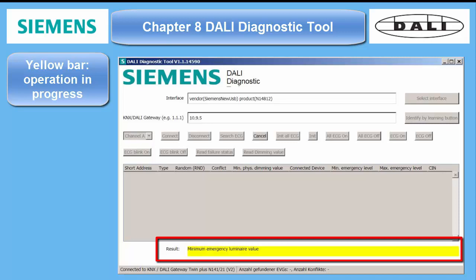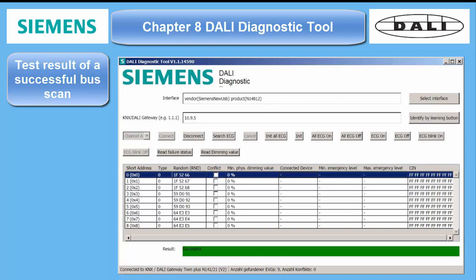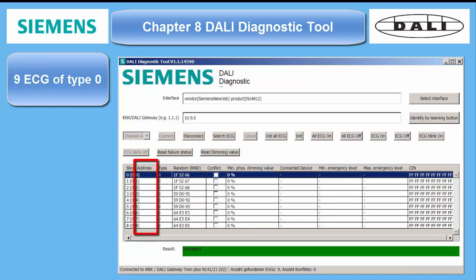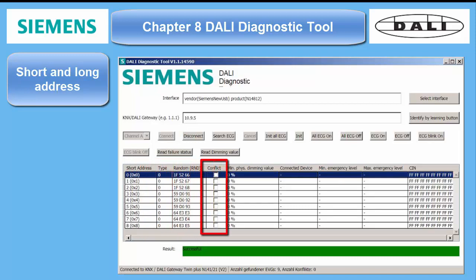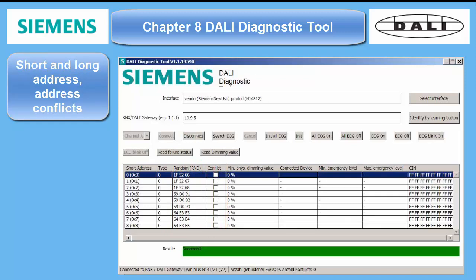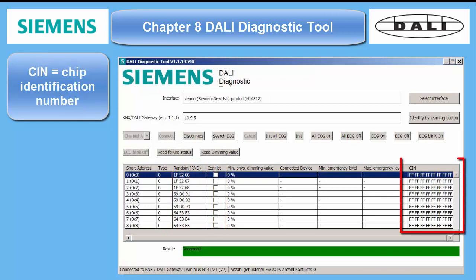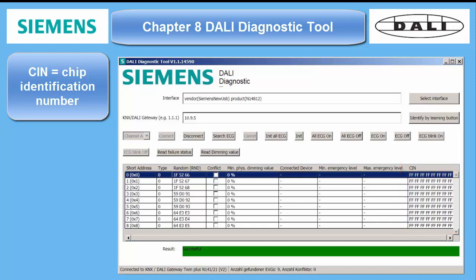Here are the various tests the tool performs to retrieve available information from the ballasts. The colors red and green in the result bar are self-explanatory. On this screen we have the fault-free result of a bus analysis after pressing 'Search ECG.' The tool has found nine ECGs, all of type 0 fluorescent tubes, though other ECG types are also possible. In my case, I used three three-channel LED drivers, which use the generic type 0. The list contains info about short and long address, the random address, if there is an address conflict, and four more properties of the ballast if available. The last column shows the CIN — chip identification number — which is currently used only by OSRAM, so no codes are visible here, with all digits showing FF.